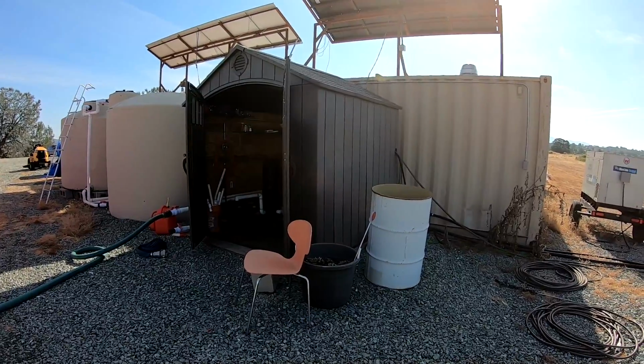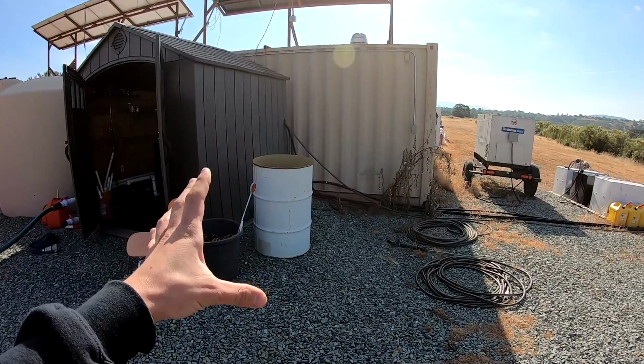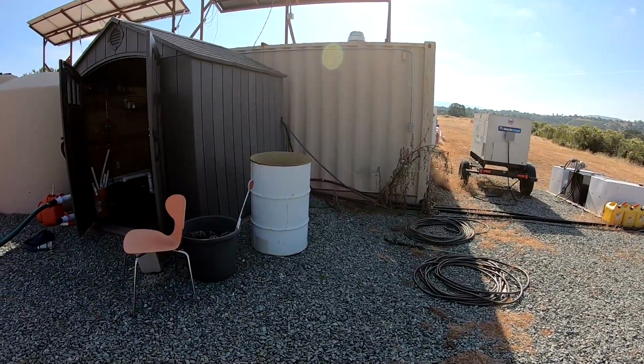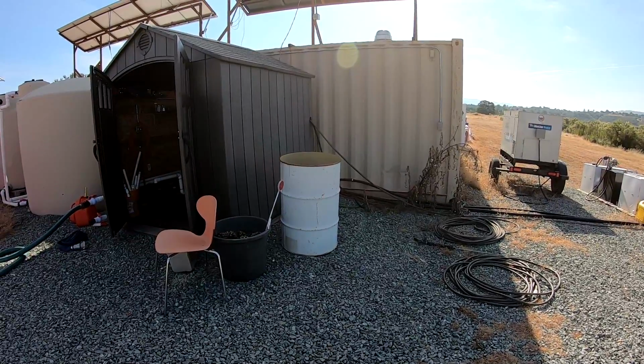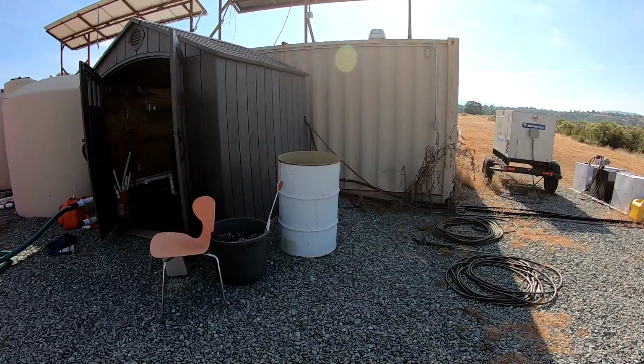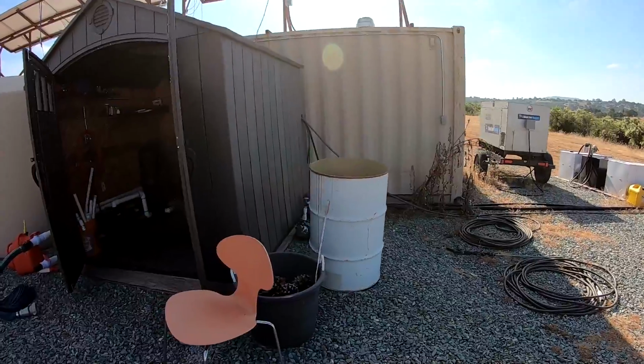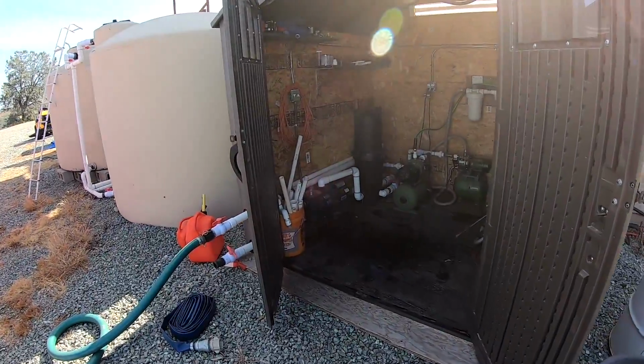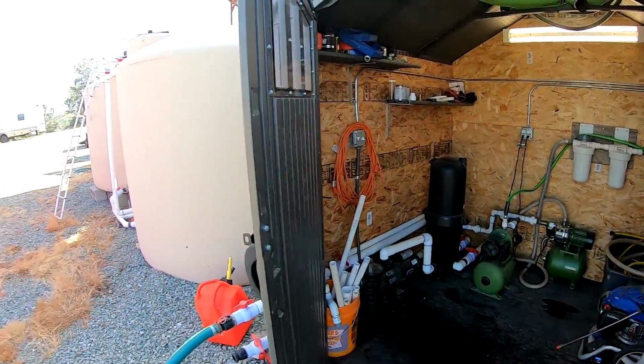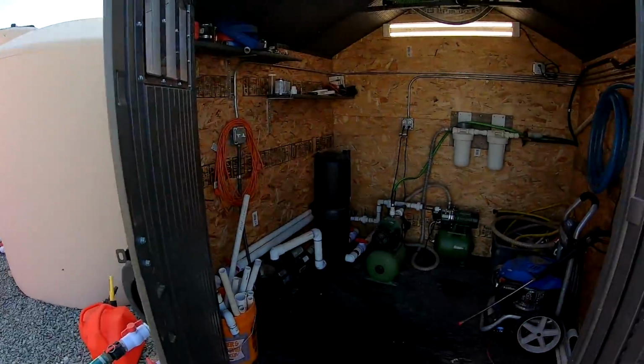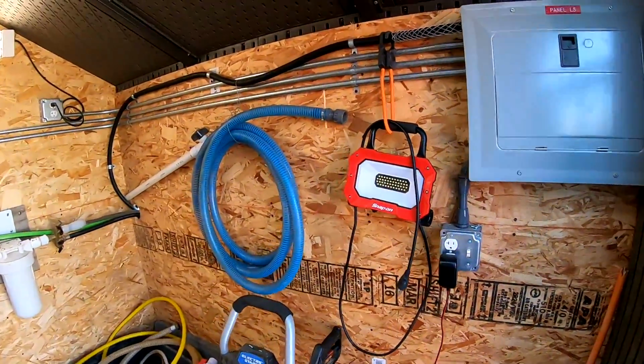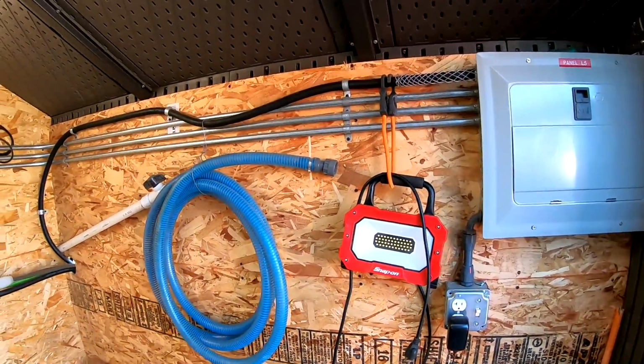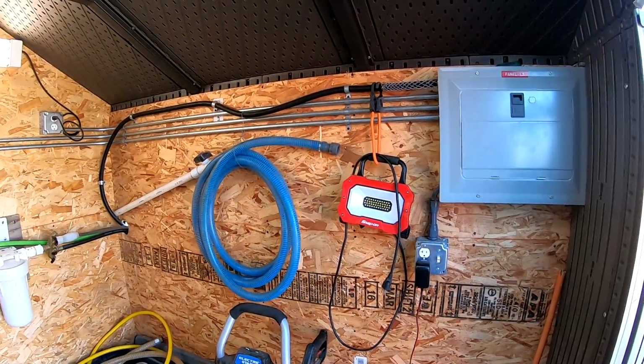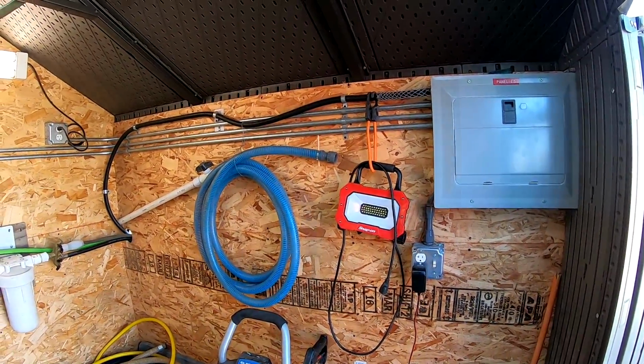Plans for the future are to eventually have that tan tank that was in the meadow placed right here, and the 2-inch pipe feeding up the hill will fill that tank with potentially dirty water. I'll then have the pool pump suck the water out of there, run it through the filter and into the other tanks. I'm going to put a PLC panel in here to control all this, connected through Ethernet to the other PLCs and the new HMI panel I'll be getting here in a week.